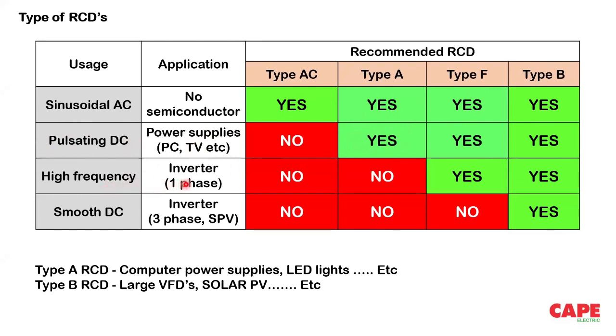Similarly, for high frequency, let's say, for example, a single phase inverter application, you need to have a type F RCD. Similarly, for a smooth DC, say a 3-phase inverter, in the sense a 3-phase variable frequency drive, or a solar PV installation without simple separation, under such conditions you need to have a type B RCD. So 4 types are there. You have to select the RCD appropriate to your application. Please note that all these RCDs are AC duty, in the sense these are for AC application. The smooth DC is a DC leakage in an AC line. Don't think that this type B RCD is for a DC purpose. It is not like that. It is for AC purpose, but the leakage is DC.